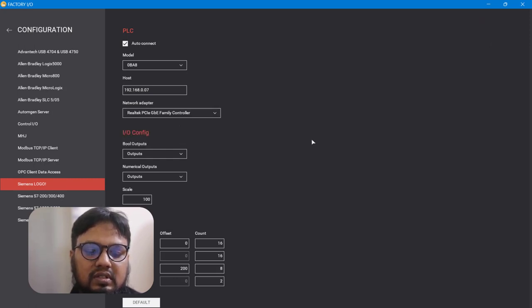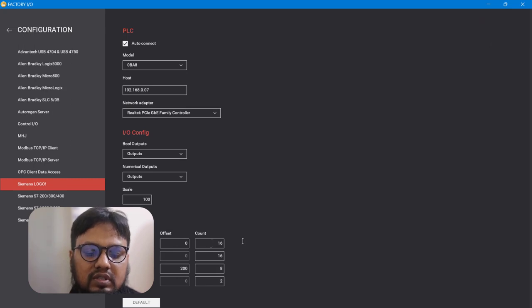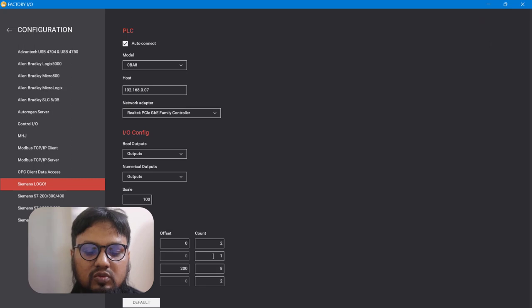In the configuration, put the IP address for your PLC, then choose the adapter — Realtek PCIe GBE family controller. From the bottom panel you can choose the number of inputs and outputs you want to use. We want two inputs and one output, so I'm entering two and one.